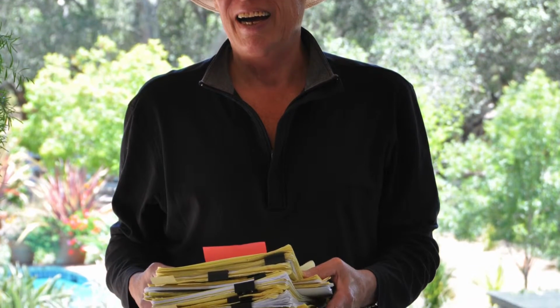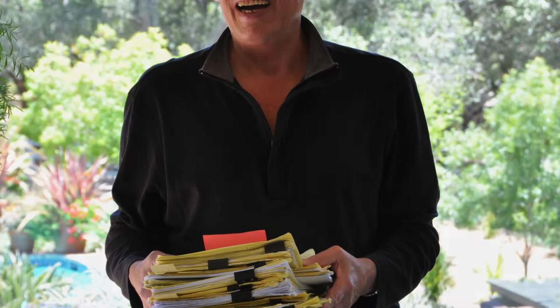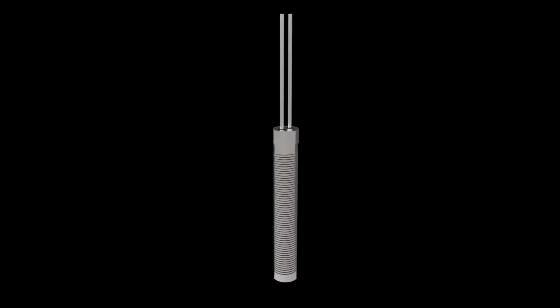On March 9, 1999, Dr. Olin patented a breakthrough thermal sensor design. Like other thermal mass flow sensors, it was made of a platinum resistance temperature detector wire wound around a ceramic mandrel. But this is where the similarities ended.